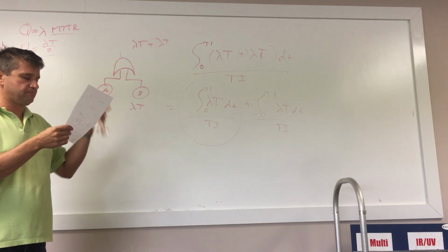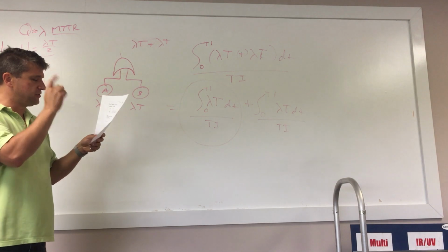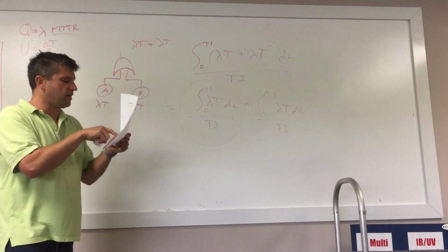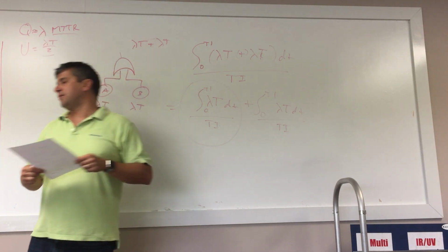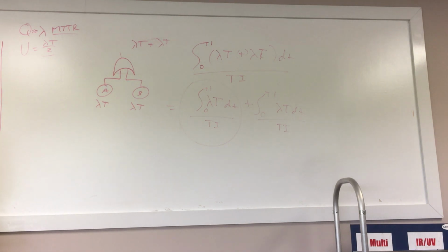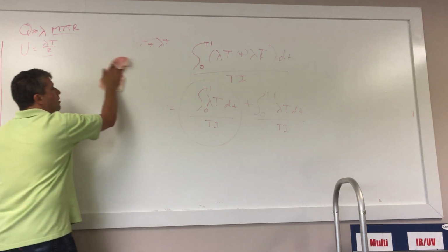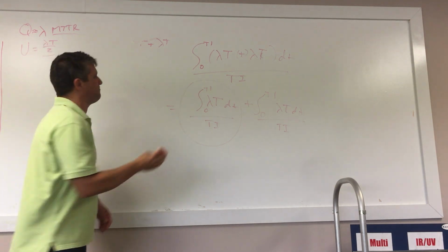The lambda DD term is using typical probability math. And the beta term is the term that is the problem. Now, why does this have a beta term? Why should you use a beta term? Does the beta term make sense for 2 out of 2? The answer is no, most of the time.